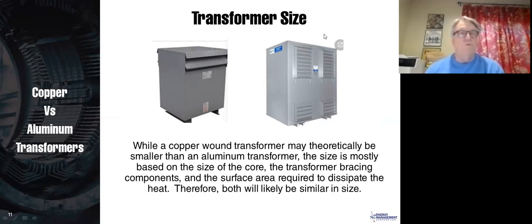So obviously, the more surface area you have, the easier it will be to cool. And if you have a liquid cooled transformer, like with mineral oil, the larger the transformer is, the more tubes you have in the radiators, the more cooling capability you are going to have. And so in theory, an aluminum transformer will be a little bit easier to cool because the conductors are larger. But in practice, either one cools just fine. The transformer manufacturer builds that thing to run at a certain temperature rise. And whether it's copper or aluminum, it will run at that temperature rise. And so here again, I wouldn't say one is better or worse than the other.